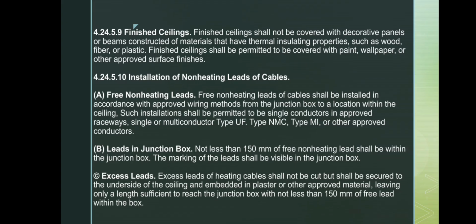Next is for the finished ceiling. Heating cable ceilings must not be covered with decorative panels or beams made of insulating materials like wood, fiber, or plastic. However, paint, wallpapers, and other approved finishes are allowed. For non-heating leads, they must be installed using approved wiring methods from the junction box into the ceiling. At least 150 millimeter of free non-heating lead must remain inside the junction box, and the markings must be visible.